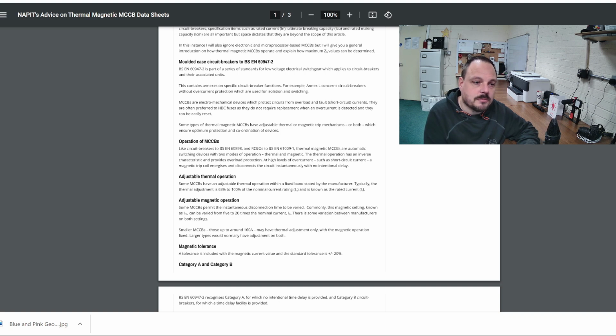And then it tells you about the adjustable thermal operation, as I spoke about earlier on, and basically you have that adjustment typically from 63% to 100%. So on that 200 amp example I had, we could drop down to 140 amps for the overload, so the thermal aspect of it, and we could leave it set to the maximum rating for the actual MCCB itself at 200 amps. And then the adjustable magnetic operation, so some MCCBs permit the instantaneous disconnection time to be varied. Commonly this is a magnetic setting known as IM, and it can be varied from 5 to 20 times the nominal current.